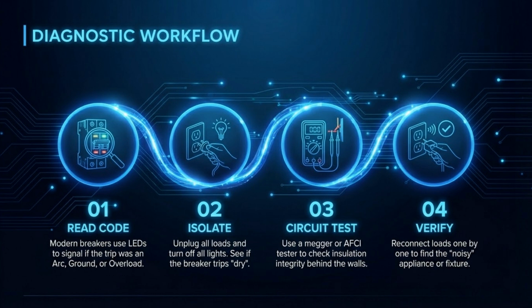Here is the diagnostic workflow. Step 1. Read the code. Step 2. Isolate the issue by unplugging loads. Step 3. Circuit test using a Megger or AFCI tester. Step 4. Verify by reconnecting loads one by one to find the noisy appliance or fixture.